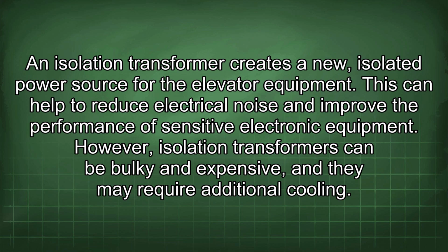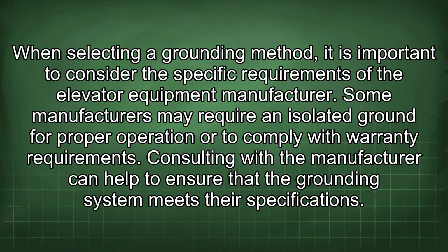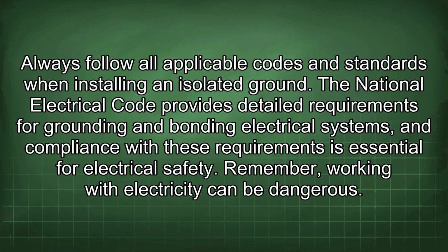An isolation transformer creates a new isolated power source for the elevator equipment. This can help to reduce electrical noise and improve the performance of sensitive electronic equipment. However, isolation transformers can be bulky and expensive, and they may require additional cooling. When selecting a grounding method, it is important to consider the specific requirements of the elevator equipment manufacturer. Some manufacturers may require an isolated ground for proper operation or to comply with warranty requirements. Consulting with the manufacturer can help to ensure that the grounding system meets their specifications. Always follow all applicable codes and standards when installing an isolated ground.